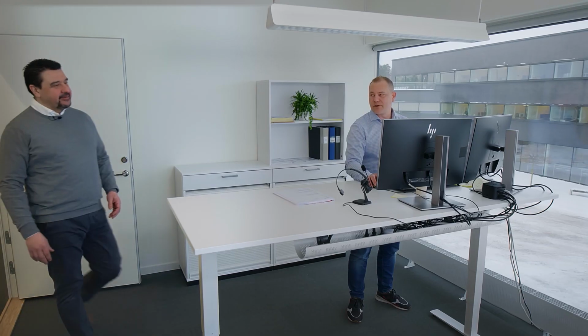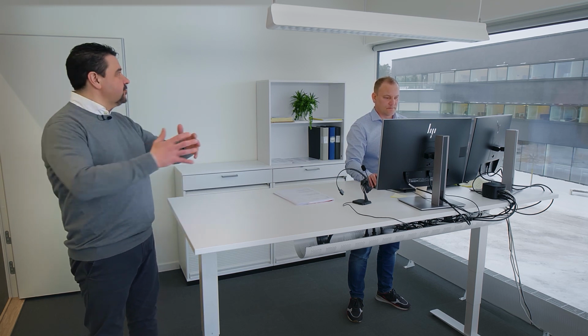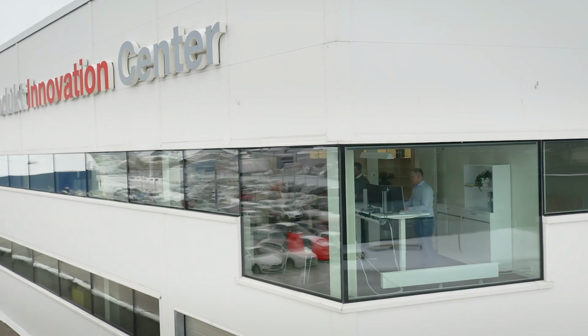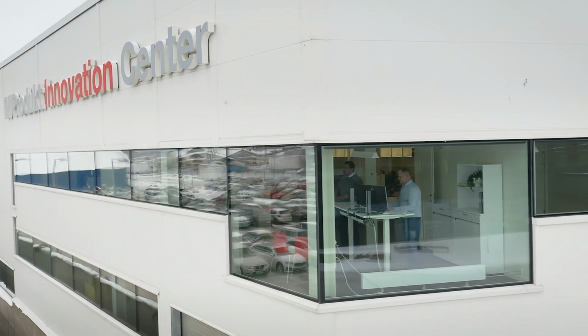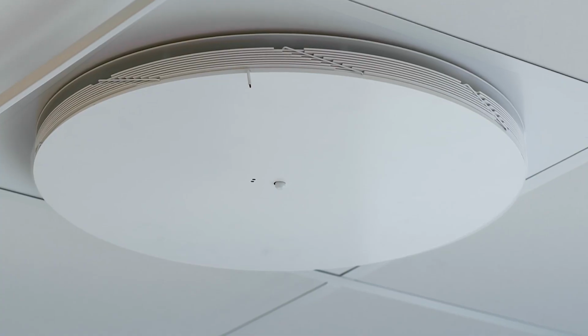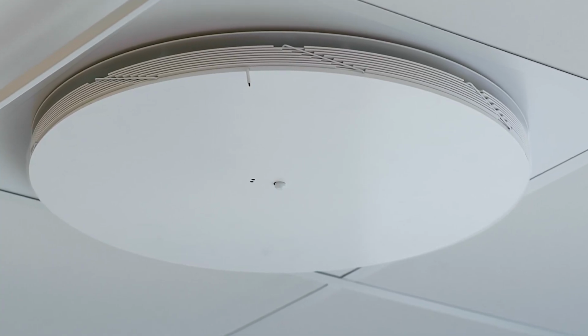Hello Per. Hey Manuel. We're now standing in a corner office with large glazing areas, and we all know it's a challenge to get a good indoor climate. Hence why we decided to work with active diffusers, where we have sensors that can sense when people enter the room and increase the airflow. But we can also sense the temperature. So if the temperature increases, we can increase the airflow.